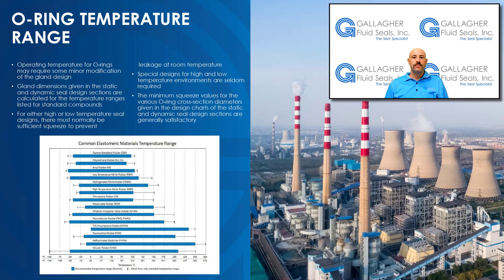Operating temperature, or more properly, the range of system temperature, may require some minor modification of the gland design. Gland dimensions given in the static and dynamic seal design sections are calculated for the temperature ranges listed for standard compounds. If the operation is only to be at high temperatures, gland volume may need to be increased to compensate for thermal expansion of the O-ring. Conversely, for operation at a low temperature, a better seal may result by reducing the gland depth, thereby obtaining the proper squeeze on the contracted O-ring.